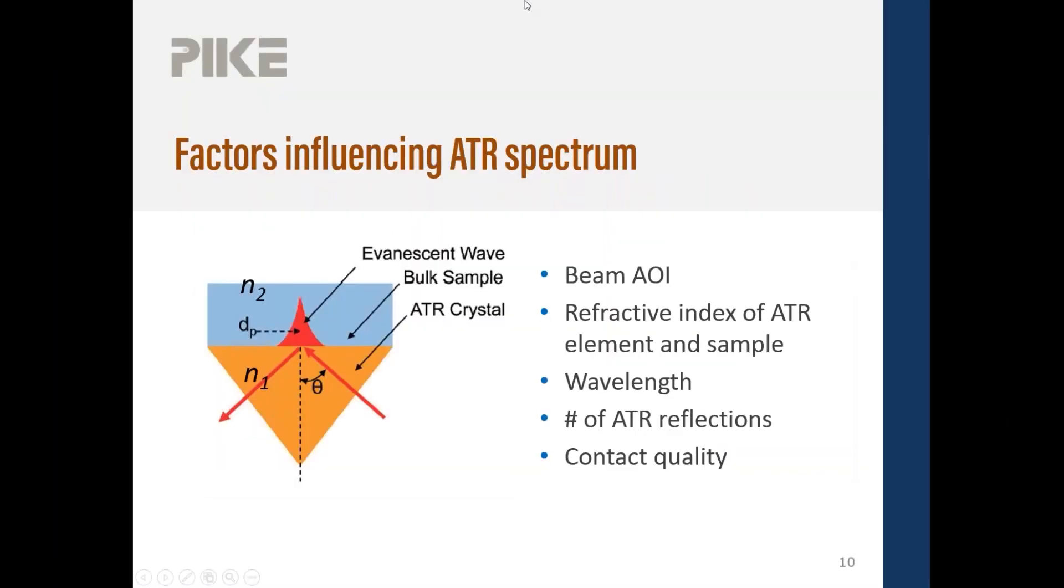So your ATR spectrum is a function of several different parameters. One being the angle of incidence for the accessory, the refractive index of your sample, as well as the ATR element. We're going to see illustrations where it's a function of wavelength, the number of reflections, and most importantly, factors influencing your ATR spectrum is contact quality. ATR requires that you have intimate contact between your sample and the ATR crystal. Without that intimate contact, your spectrum bands may not be as strong.